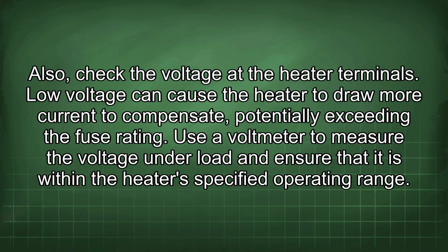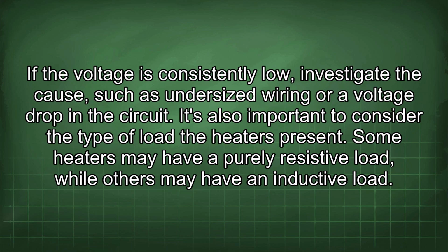Also, check the voltage at the heater terminals. Low voltage can cause the heater to draw more current to compensate, potentially exceeding the fuse rating. Use a voltmeter to measure the voltage under load and ensure that it is within the heater's specified operating range. If the voltage is consistently low, investigate the cause, such as undersized wiring or a voltage drop in the circuit.